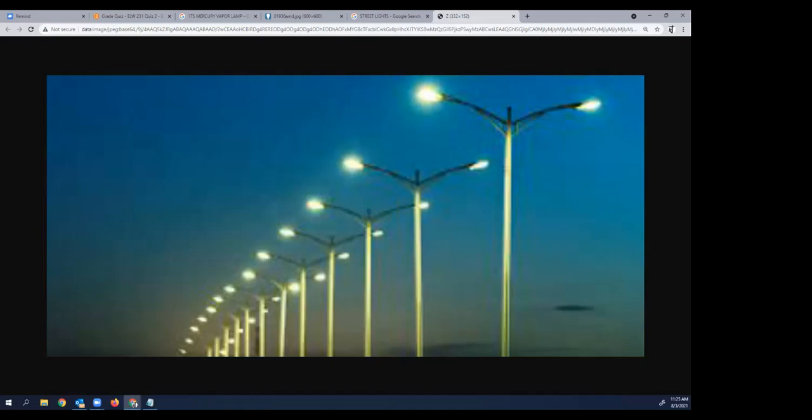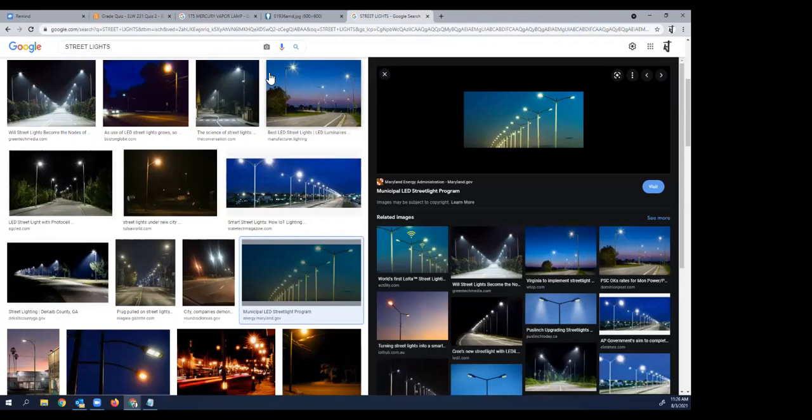What size wire do I need to feed all of these lights? Number 12. I mean, underground. That's 1, 2, 4, 6, 8, 10, 12. That's an engineer decision, but I can guarantee you, he's going to oversize it just a little bit to make sure you got a safety factor in there so things don't burn up. If these are 400 watt lights, 1, 2, 3, 4, 5, 6, 7, 8, 9, 10, 11, 12, 13, 14. What's 14 times 400? 5,600 watts, right? Heck, I almost need a 10 kVA transformer just to feed the lights. So a lot of it's safety factored in there, Lenny.